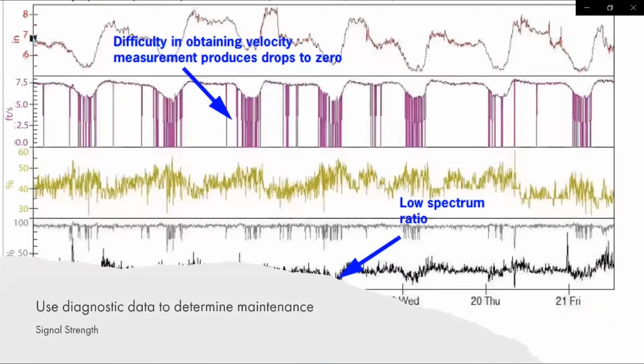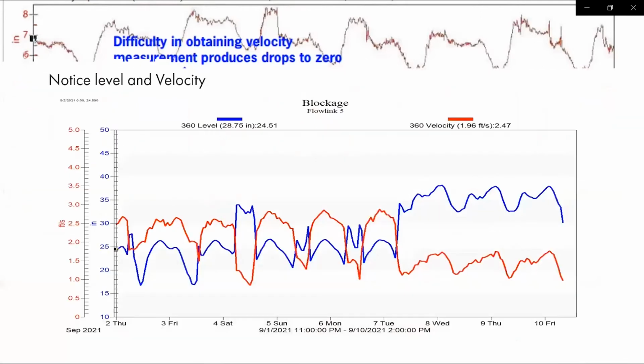And this is just an example of some of the diagnostics. So what we're showing is the velocity, you're getting a lot of dropouts, which could be from debris. And then you're looking at your signal and the spectrum strength. Usually you want it above that 40%. If it starts dropping, that's an indication that we may be having problems. So whenever we have the dropout on velocity, we're starting to get a low spectrum strength. And in this image the ratio is starting to drop too, indicating that there was debris in that channel. In this particular case, it had some lower levels that were causing some problems.